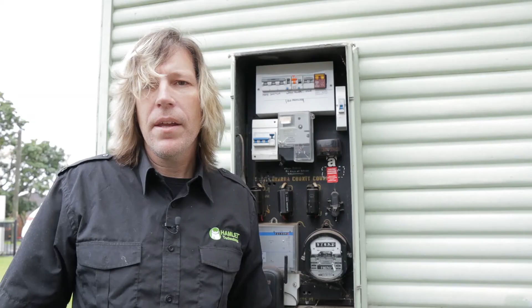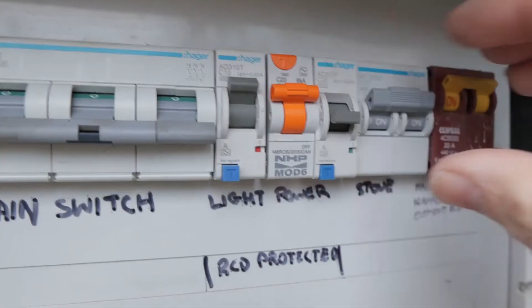Okay, so here we are. This is the main board to the house. And the issue we've got is this circuit breaker, or RCD, which is tripped and won't reset. You can see here that if I try to reset this, it's just not doing anything - it's jammed, it won't go that way, and it's not doing anything that way, which tells me straight away that this is definitely faulty, and that's what we're going to have to replace.